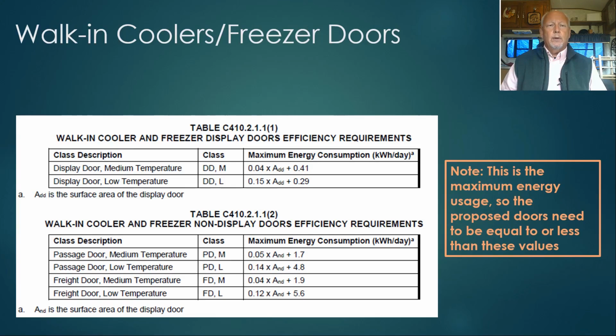In researching some of these requirements, I noticed most manufacturers of walk-in coolers and freezers are already on board with these new DOE standards and are labeling their equipment accordingly. If you have passage doors, non-display doors, then depending on the temperature, the capacity of the system, and the size of the door, you have another maximum energy consumption value in kilowatt hours per day. So find your door, find the value, and then you can determine whether the door meets that standard. Again, the manufacturers are beginning to label their doors or publish their performance data, so this should be easy to verify. Note that this is a maximum energy usage, so the proposed doors need to be equal to or less than these values.